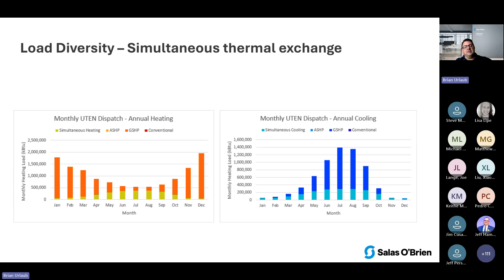But again, back to the flow rates. On the left would be your flow rate for a 5-degree delta between the four buildings. That's fine, but with an open loop system we don't need to do that, because we're still just providing fantastic medium temperature to the buildings that's extremely efficient. So we went to a 12-degree delta just to model it and see what it looks like. Look at the difference in pump energy and flow rate: we went from 2,200 gallons a minute on our peak to under 1,000. We cut everything in half.